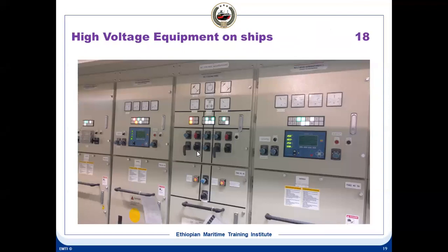So all the paralleling, everything can be done from here. You can see it has a synchronoscope here. It has a lamp method also. You can use either of these methods to synchronize. You can do this manually or through the power management system. This is the power management system, known as the HIMAP. It takes care of the full power management, like starting and stopping generators, or even auto synchronizing and load sharing. Everything is done by this HIMAP.